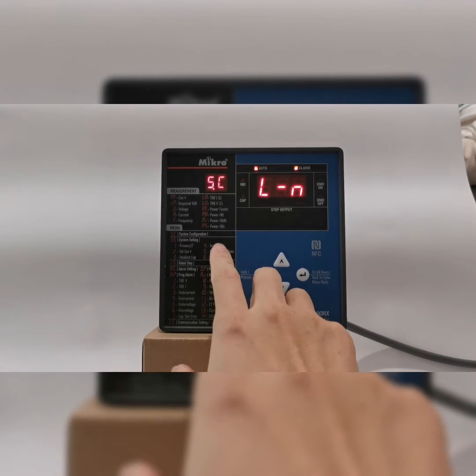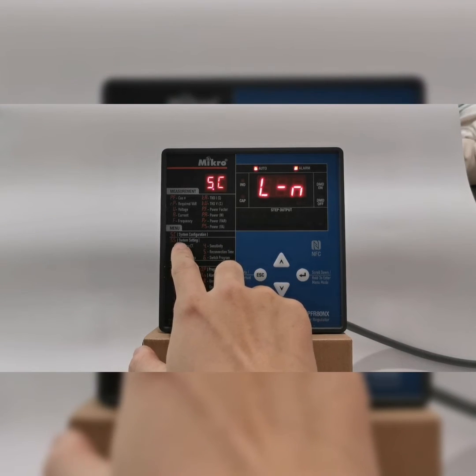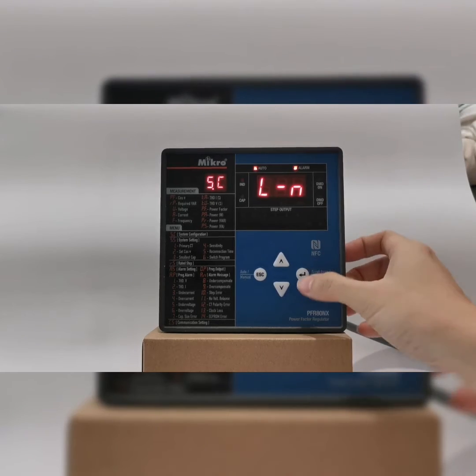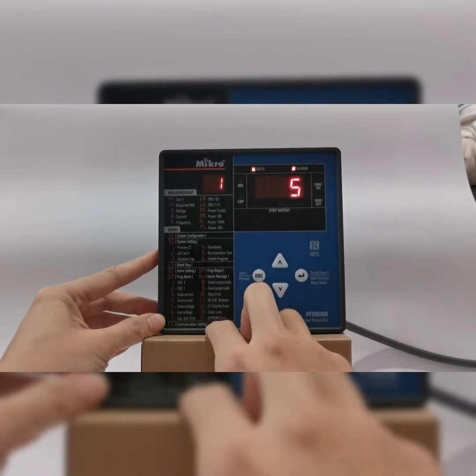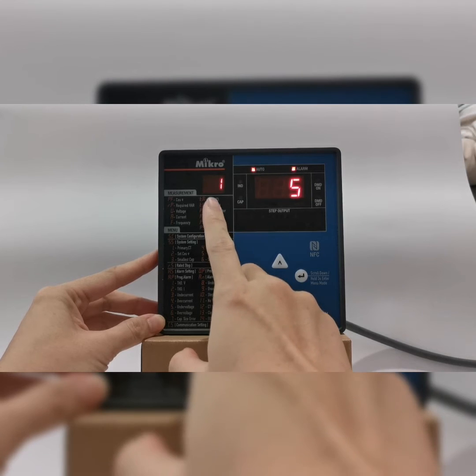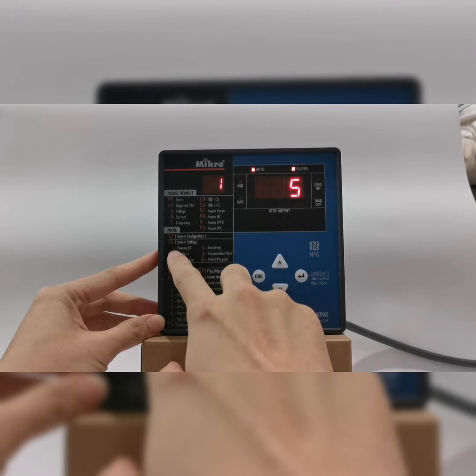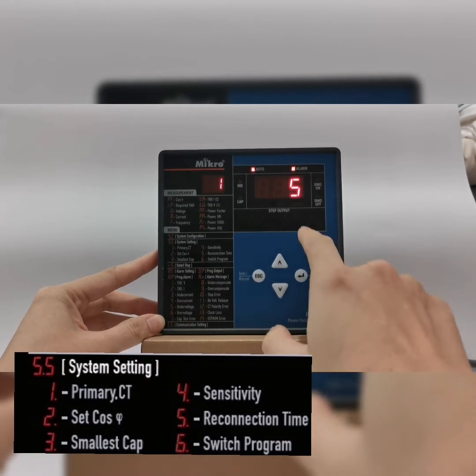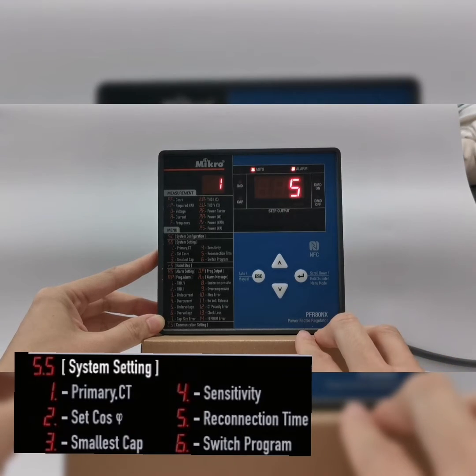SC1 means system configuration, but we need to go to system setting, so press enter again. Now it's SS1. SS1 means primary CT setting. Currently its setting is 5.